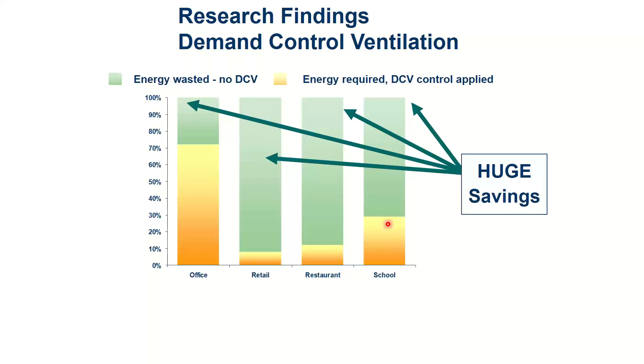Paybacks are pretty quick on demand ventilation because the sensors are inexpensive and the damper system is already typically there. The control system on the dampers, in most cases, can already handle this, so I'm literally just adding a sensor and turning a few features on. It's pretty easy and quick payback for a lot of these spaces. The more heavily occupied the space, and the more variable the occupancy, the faster the payback.